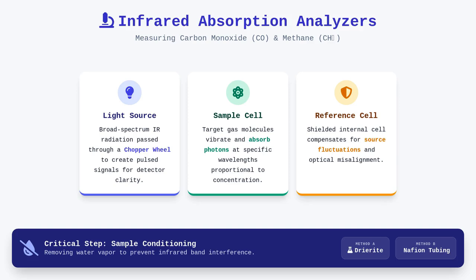As water vapor shares infrared absorption bands with the gases we measure, we typically employ Drierite, an anhydrous calcium sulfate, or specialized Nafion tubing to strip moisture from the sample gas stream, ensuring that our readings remain accurate and free from humidity-induced interference.